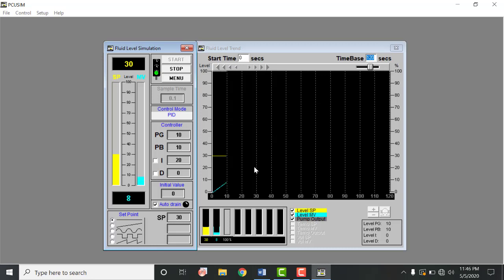Okay, so it means that we have given the command to our controller to start reducing the output of the pump when the difference is 10. So from the 20 point it would start that deceleration. Now at the 20 point you can see that the power output of the pump is reducing, and it is gradually and slowly achieving the output value. Now you can see it depends on you whether you want a quick response.